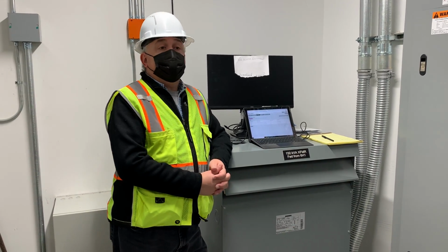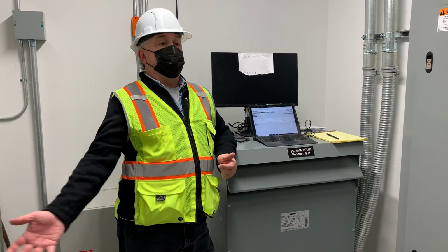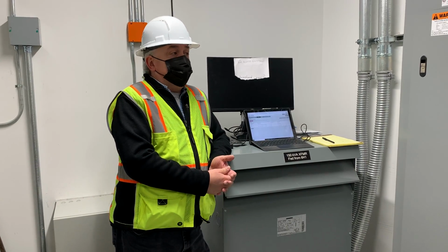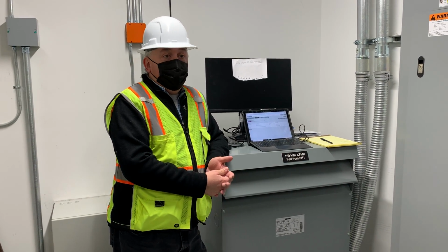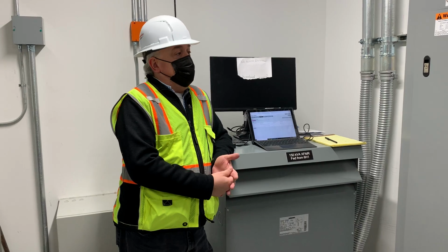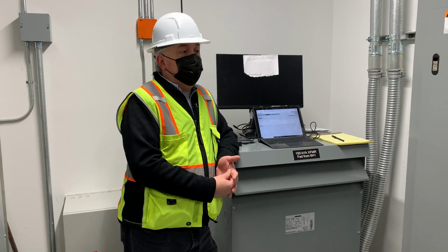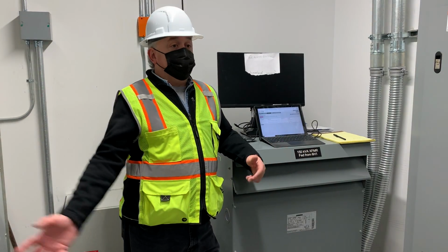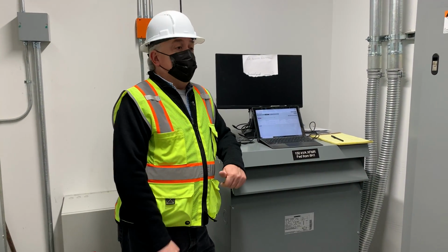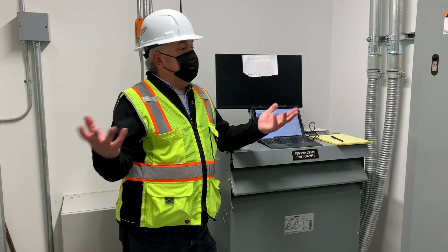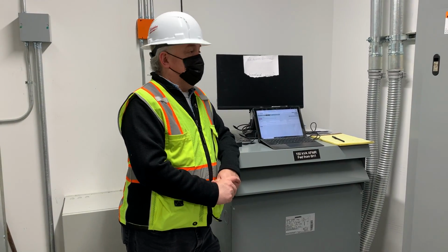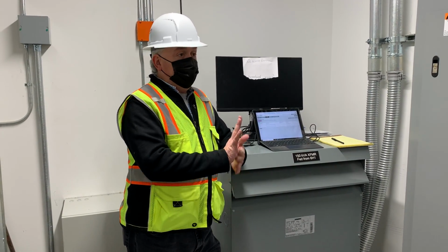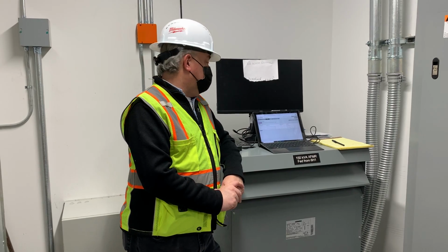If there's the desire to tie it into BACnet, this is very, very BACnet friendly. So you can do BACnet over IP if you want to put it onto a common building network with your HVAC and access control or anything else. Again, it isn't set up for that at the moment because we're not connected to a network, but if in the future that becomes a desired thing, then yeah, we can export a BACnet points list and say here are the things that you can control or monitor.